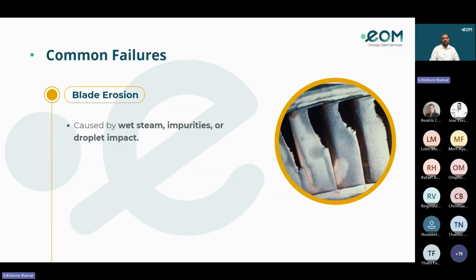Blade erosion. It is a common failure in steam turbines. It is caused by wet steam, impurities, or droplet impact. Blade erosion in steam turbines is a critical maintenance and reliability concern. It refers to the loss or deterioration of blade material due to mechanical, thermal, or chemical processes, most commonly from the impact of moisture droplets, solid particles, or aggressive chemical compounds in the steam flow. Now, the causes of blade erosion in steam turbines.